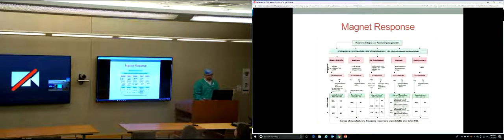So this is that table I mentioned. You can see Boston Scientific sets there. If you place a magnet and you do get a response, the BOL is the beginning of life. And then ERN and ERT are looking at different points of that battery life, and that looks at time to replacement. So as the battery life dwindles, the actual response to magnet placement will change. So it's difficult to actually say, I put the magnet on, and the backup setting was that it paces asynchronous at 100.